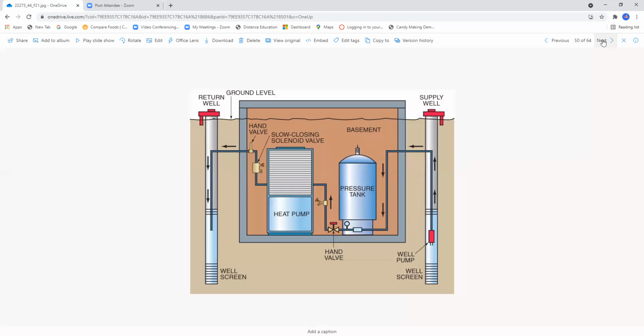We talked about this previously in the PowerPoint presentation, but we'll just refresh your memory here. If you take a look at this particular illustration, this is going to be 44.21 on page 1337. Basically, this is a return well system where you have a supply and return. So you bring the cold water in, go through the pressure tank, go through the heat pump, and of course the heat that was picked up is rejected here, and eventually this water will cool down.